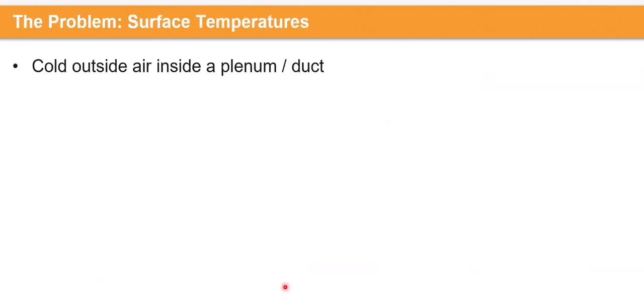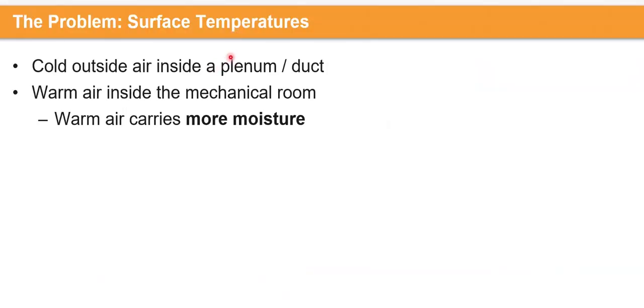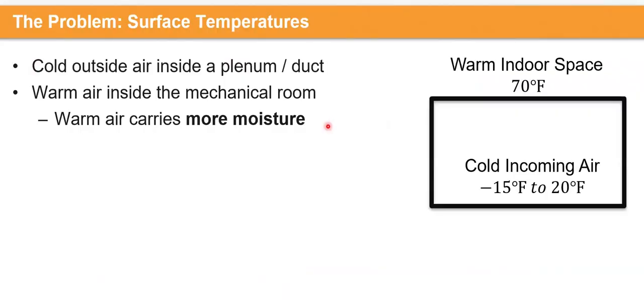Why is it super important? In the winter, when you have outside air coming into your plenum or your duct, and you have that interfacing with warm air in your mechanical room, your warm air would carry more moisture since it is warm. Here's the scenario. Incoming air is fairly cold, -15 to 20, and you have your warm indoor space that's around 70. This could be an air-conditioned space, your mechanical room, or simply just a walkway or a pathway or a hallway in a space.